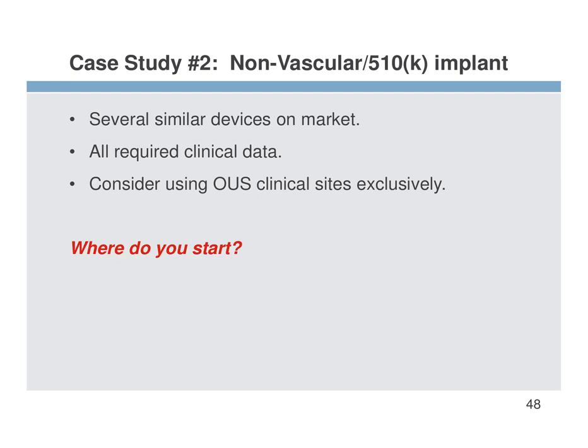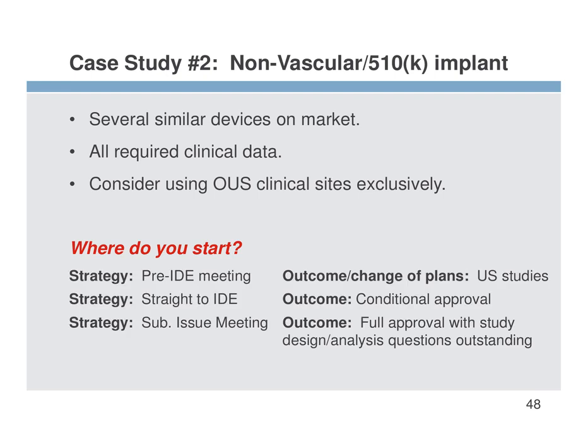Well, if we were hankering to get moving, we might just send it in as a 510K, but we actually did have some time. So we scheduled a pre-IDE meeting, a pre-sub meeting, and based on what they said would be required of the data, remember we didn't actually give them the data, we gave them an outline of what kind of data they were going to be seeing in the submission, we came to the conclusion, well, for all that, we might as well just go ahead and have a U.S. study. So we sent them in an IDE, and we got a conditional approval.